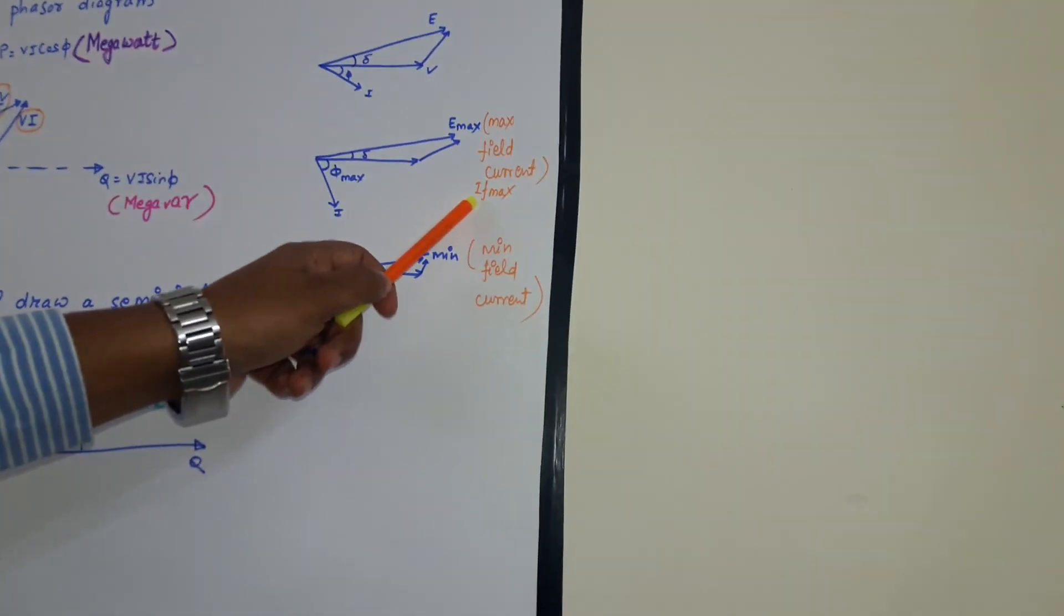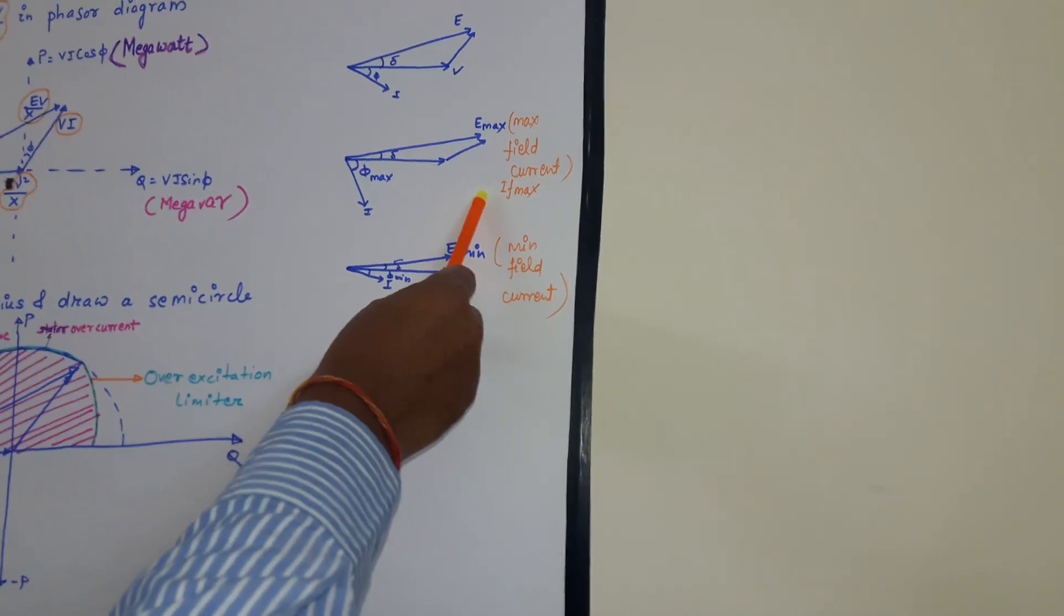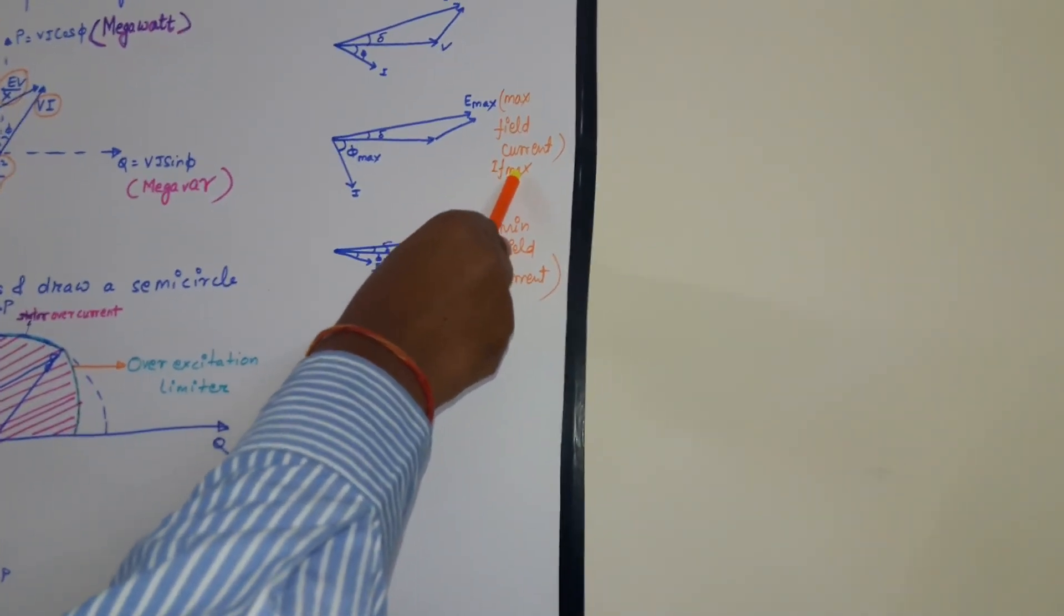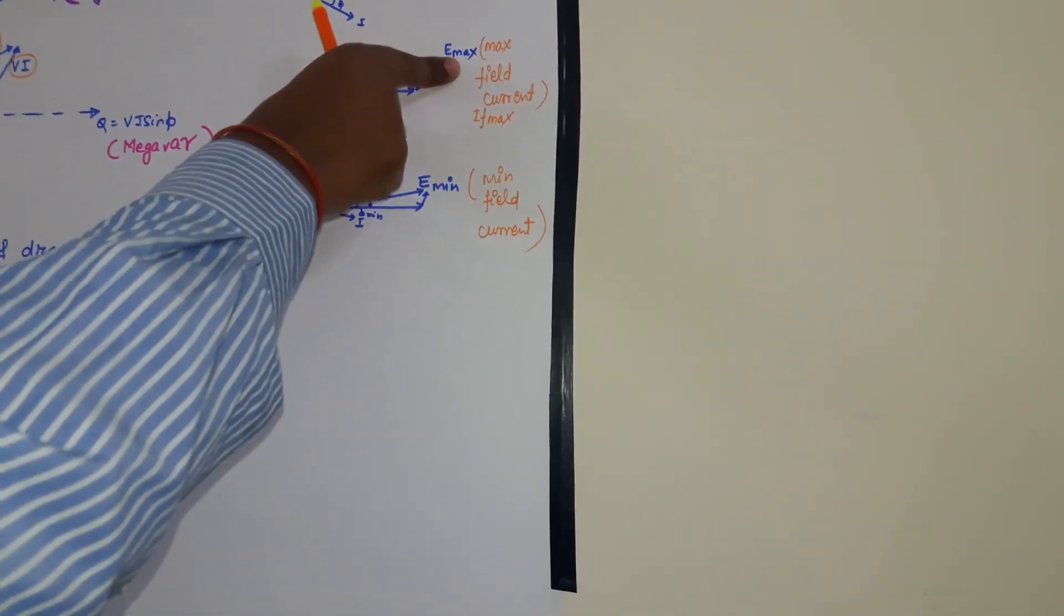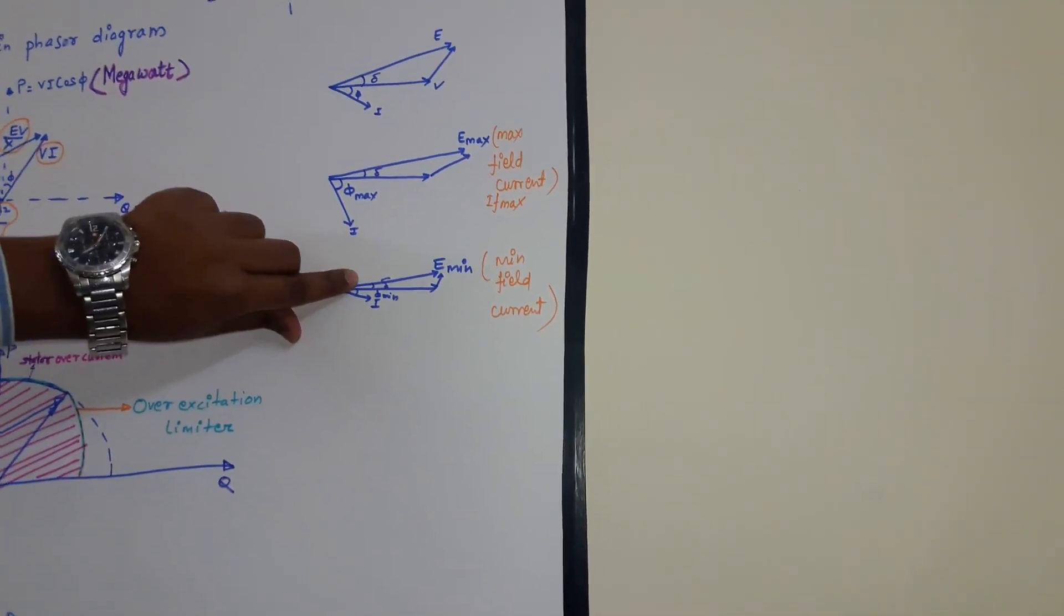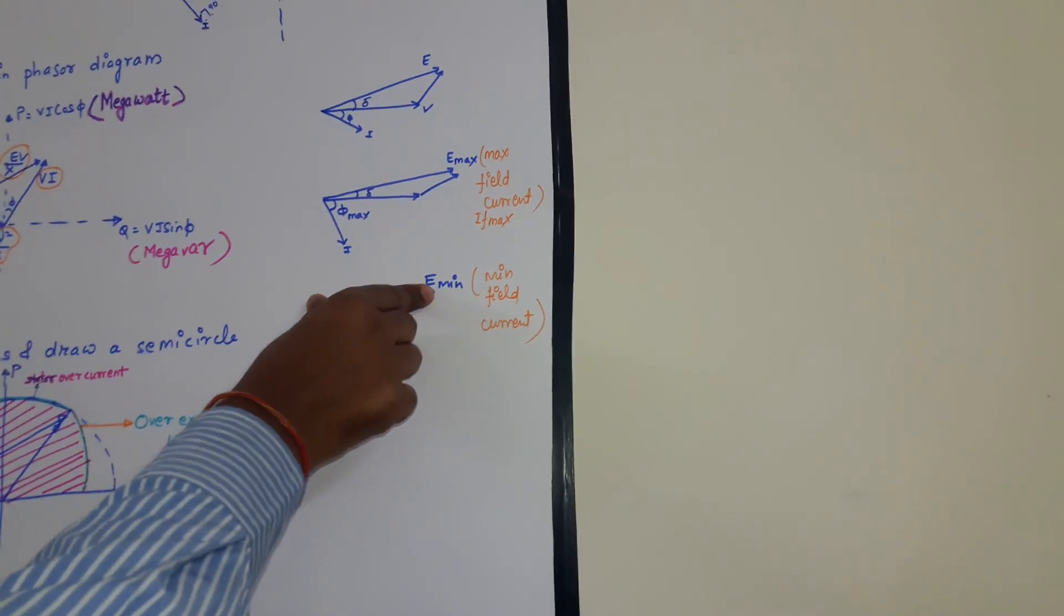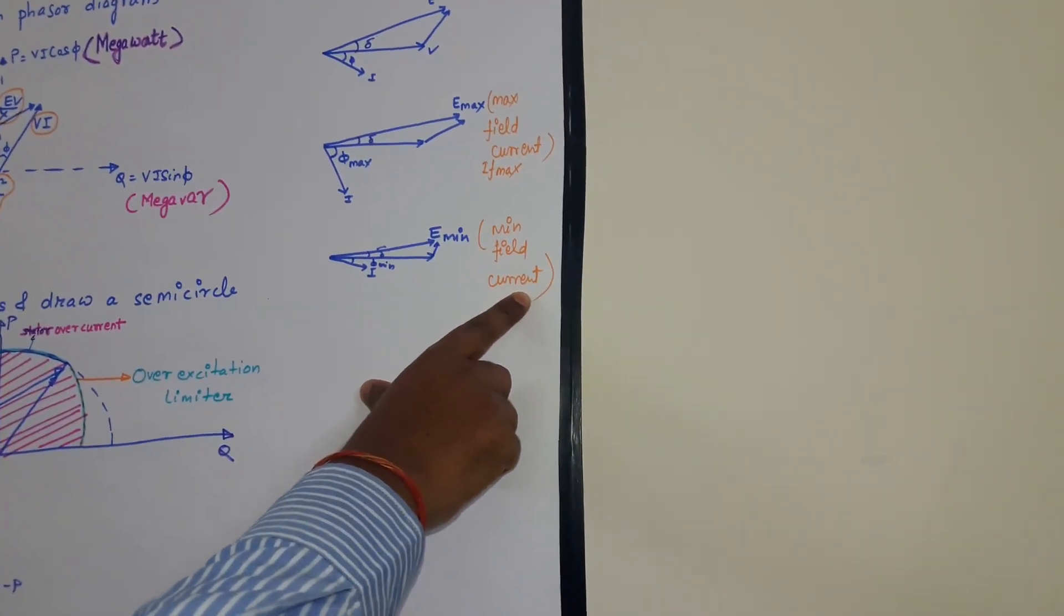And this field current is absorbed by the rotor winding. So the rotor winding has certain limitations. Beyond IF max if we will inject field current, the field winding may damage due to overheating. So E max is the maximum limitation.